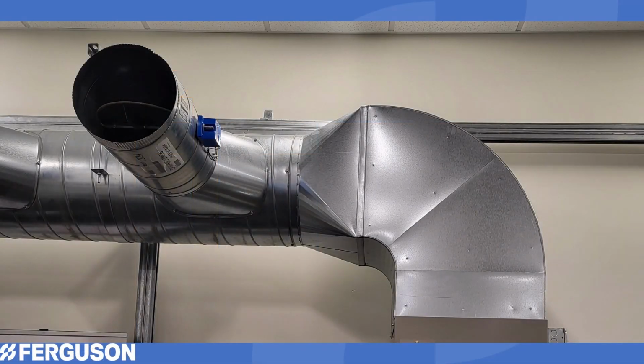So as we've stated, in your ductwork, we want to see the least amount of right angles as possible. We want to direct the air out of the furnace or air handler, and we want to direct the air into the expanding ducts off of the main branch. This will greatly reduce your external static pressure and give you the needed CFM to operate the system correctly.